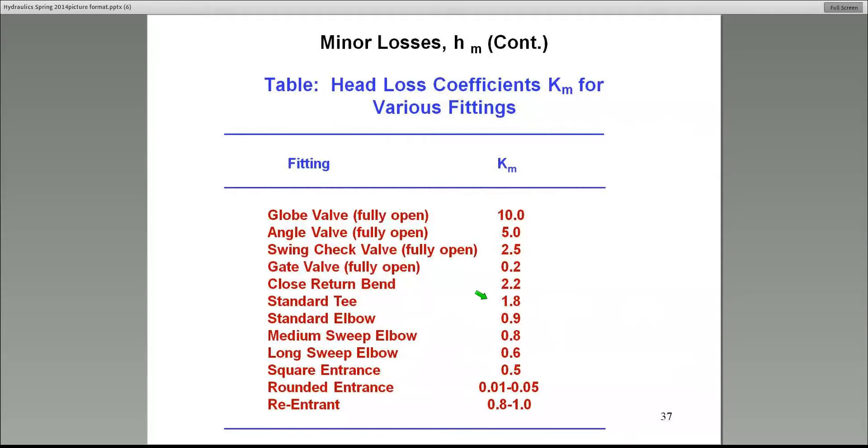Here's the typical K_m values. These are the minor loss coefficients. For example, a fully open globe valve is 10, an angle valve 5. You'll also have to sometimes deal with what we call entrance losses and exit losses. Those K_m values are given at the bottom of the table.